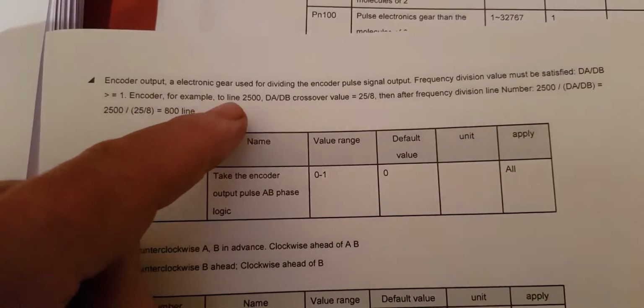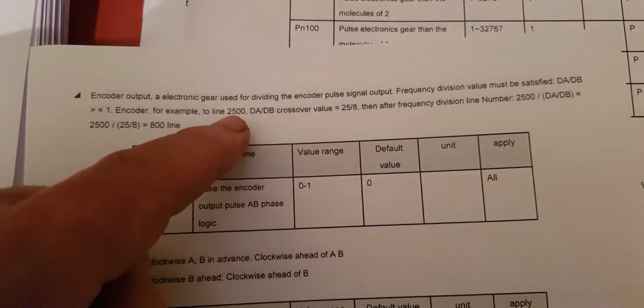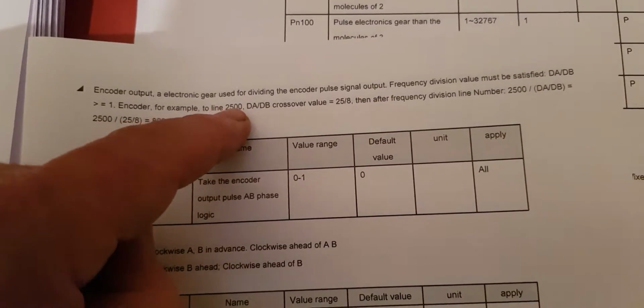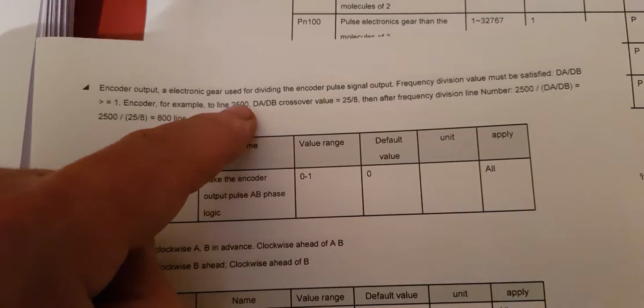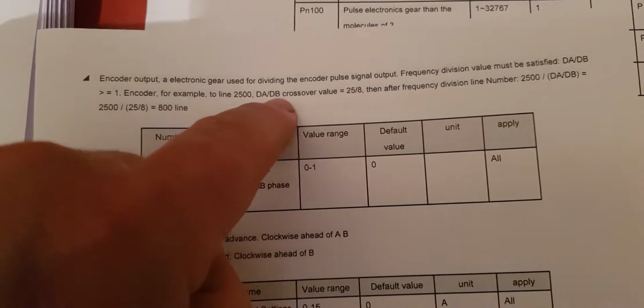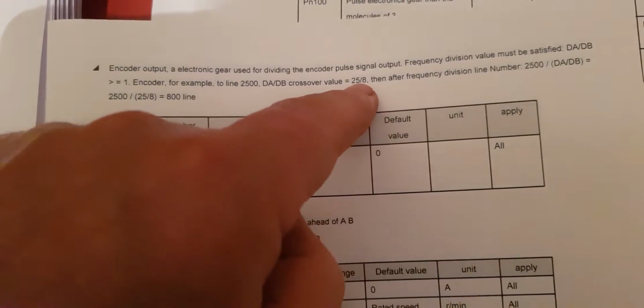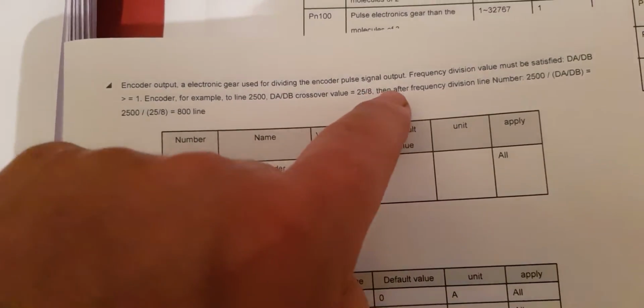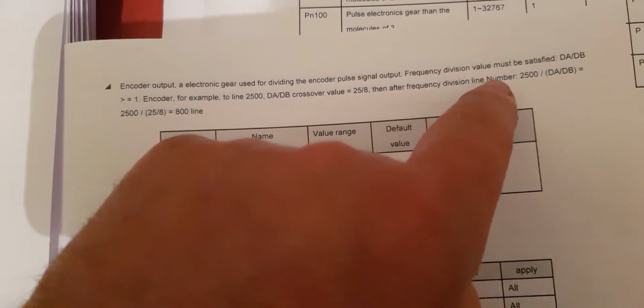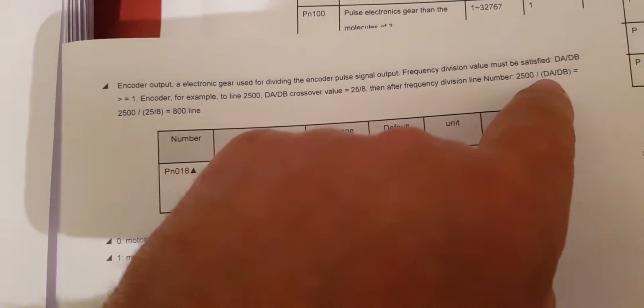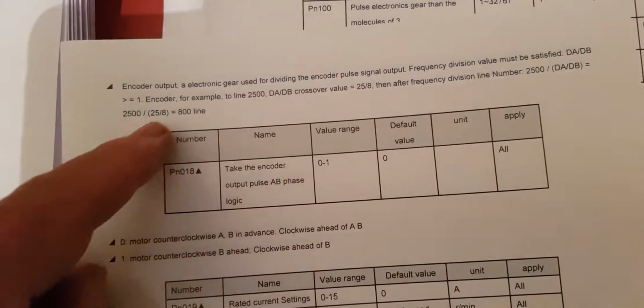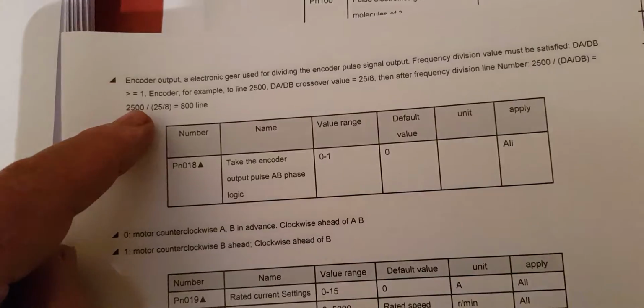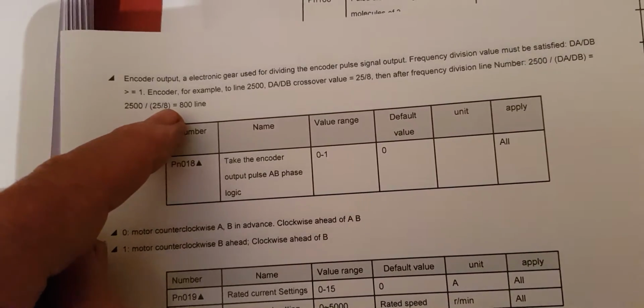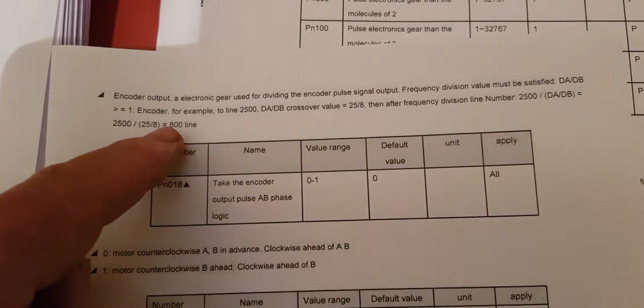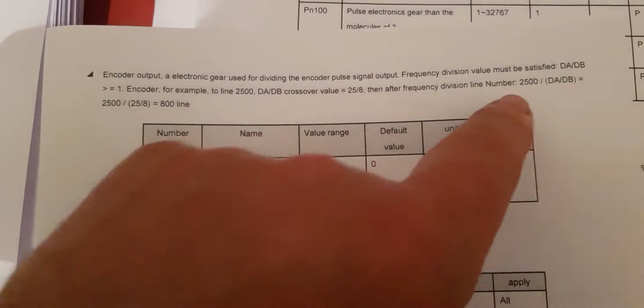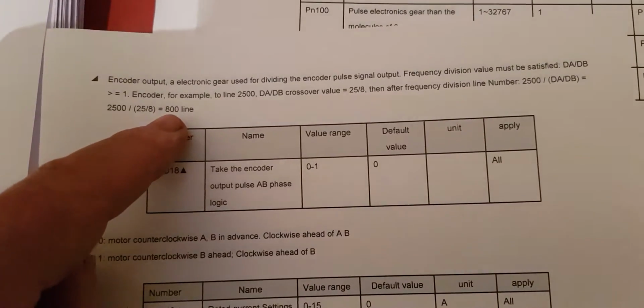But it does give you an example. They're using a 2500 line encoder, but they're not doing it quadrature, so they're just using the base count. The frequency division value is DA divided by DB, so they're using 25 divided by 8. Then after frequency division, line number 2500 divided by 25 divided by 8 equals 800 lines. So effectively, they took 2500 lines and divided it and ended up with 800 lines.